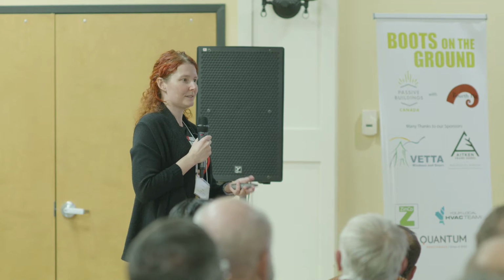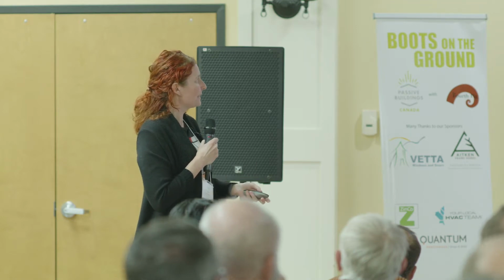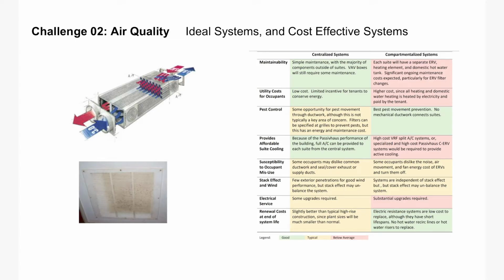Now, we've talked about the fact that these buildings are 90% more efficient than a typical building, but with low-income housing, we're still trying to think about giving people an energy source for their heating that is as cost-effective as possible. So we wanted to go to a heat pump system rather than an electric resistance heater. That drove us to a centralized system where we were able to decouple the domestic water heating, which was initially intended to heat the ERV air after it came through, and went to a centralized system.